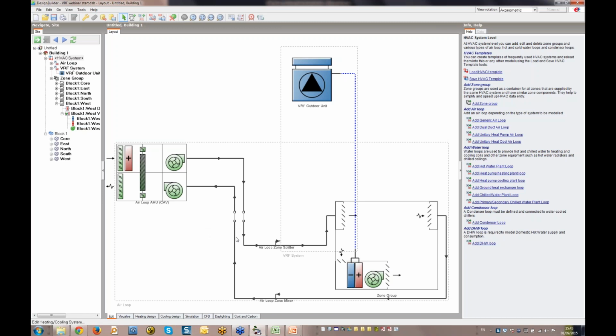The system configuration shown is fine for moderate climate conditions where the heat recovery device will ensure that the supply air temperature doesn't deviate too far from the zone set point temperature. The schematic shows the air loop supplying and extracting air to the zones via simple supply and return air grills in the zones. Should you have more than one zone group, where for example you have a central ventilation system but multiple VRF systems serving different parts of the building, the DOAS system could also supply those by adding connections via the air loop splitter and mixer.